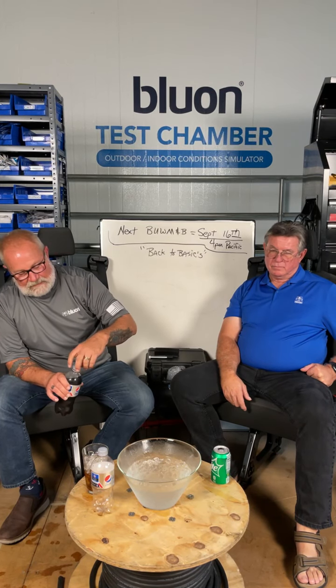On the indoor unit, would it be wise to line the box with insulation to prevent sweating? I noticed boxes sweating at times and would like to see if this is preventable. Yes, it is preventable. It depends where it's sweating too. If the unit is in the garage, non-conditioned space, in an attic, underneath the house, in the basement.